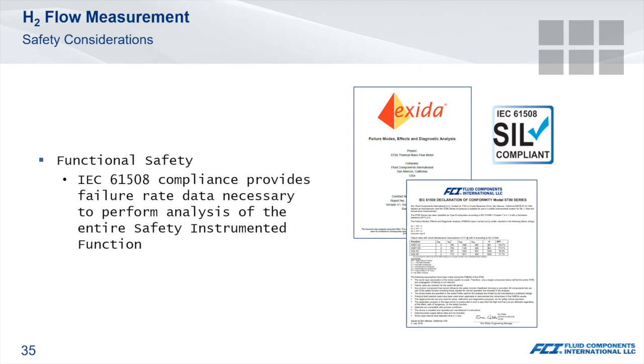Another item of interest within the process industries is functional safety. This might further limit your options when reviewing different product offerings. You will want to verify with vendors that their product has the appropriate pedigree. Without failure rate data, preferably verified by an authorized third party, performing a suitable analysis of a safety instrumented function that accounts for the logic solver, final element, and sensor is challenging. Safe failure fractions and safety integrity levels alone are not enough to be thorough.